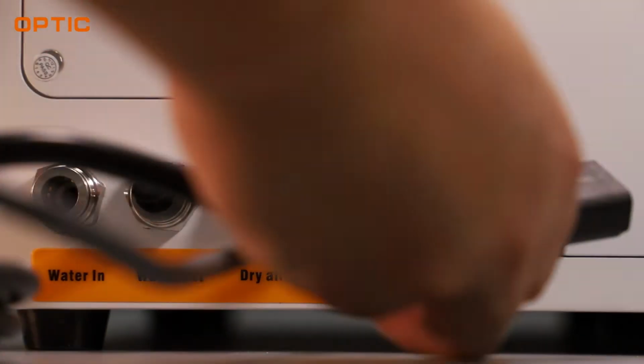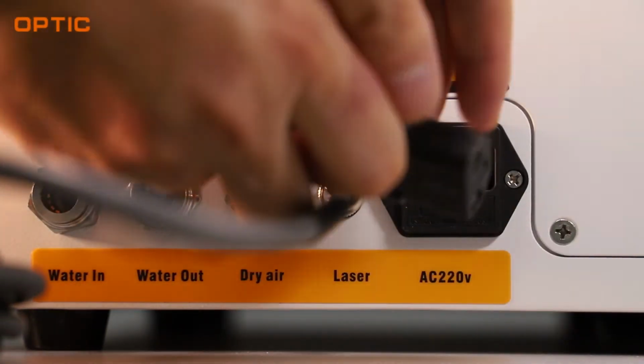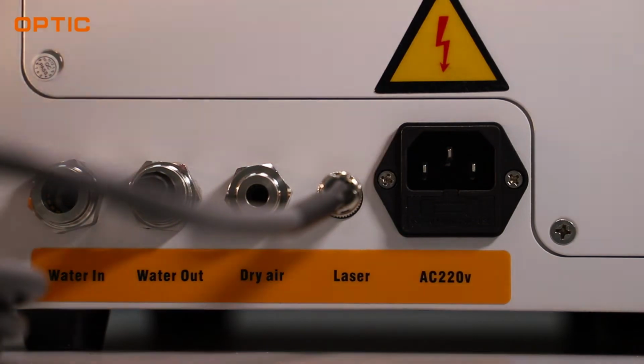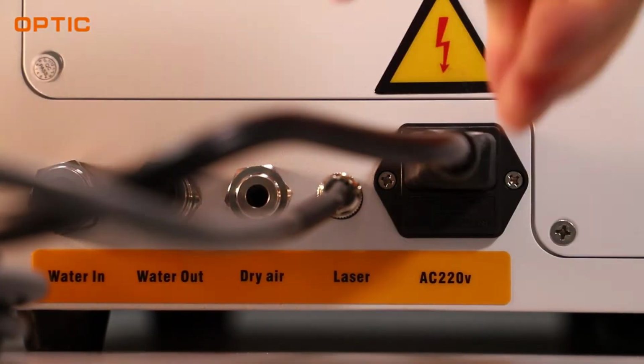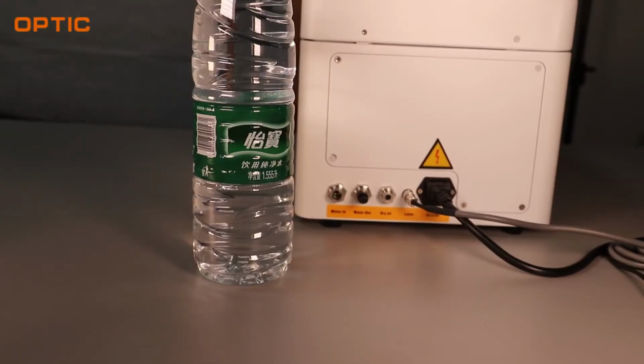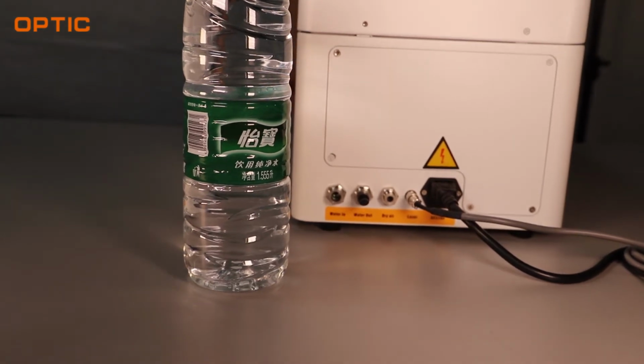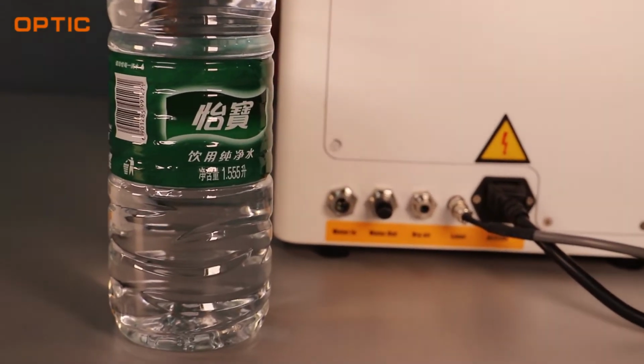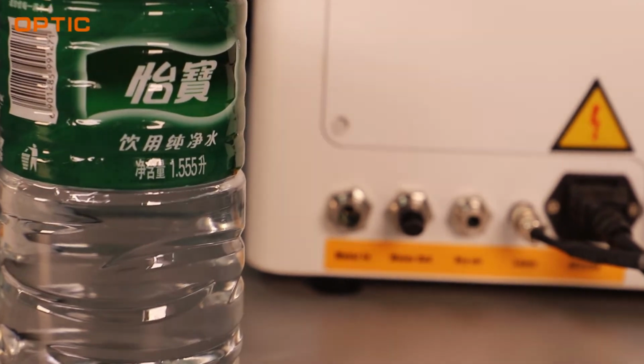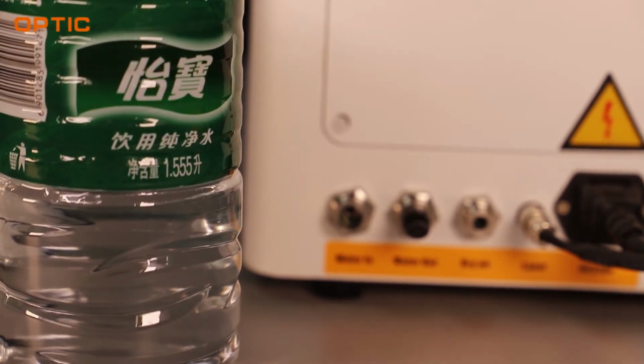Next step, connect the laser foot switch and power supply. Prepare 1.7 liters of purified water or distilled water. In order to protect the life of the machine and the cooling effect, pure water or distilled water can better protect the optical system of the machine.